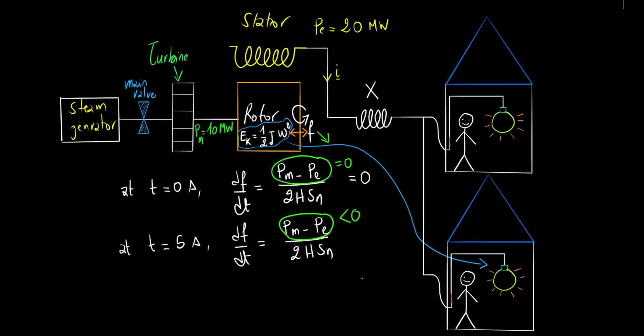The rate of this frequency drop depends on two factors: the additional power demand and your system's inertia. The higher the inertia, the slower the frequency drops, buying us valuable time to respond and restore balance. Think of inertia like your system's built-in battery, temporarily providing energy until you get things back on track.